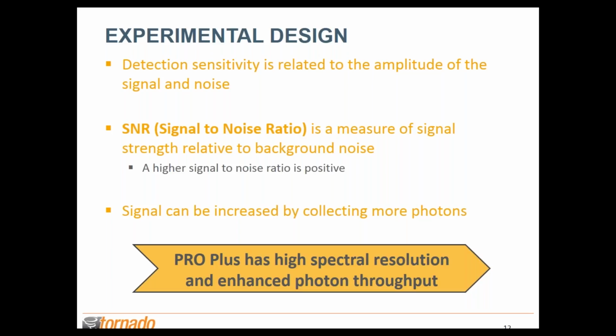The signal can be increased by collecting more photons. That'd be more light that's returned, scattered by the sample when exposed to the laser energy. And it's such that the Pro Plus was an ideal system for that, and then we have an enhanced photon throughput, and ultimately I'll show through the course of the study how that results in better sensitivity, as well as, in combination, doing so at decreased exposure time requirements.